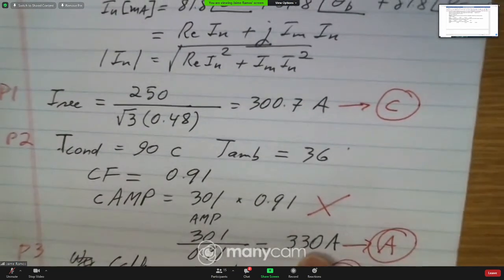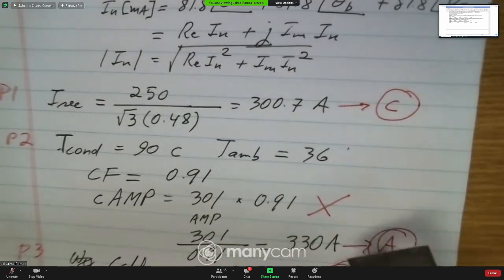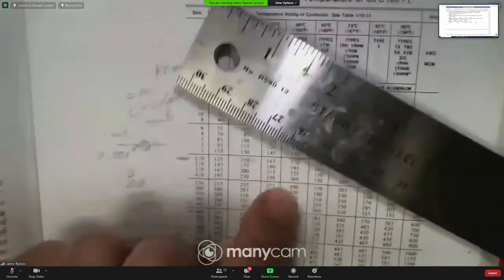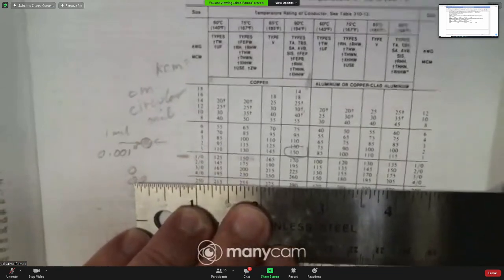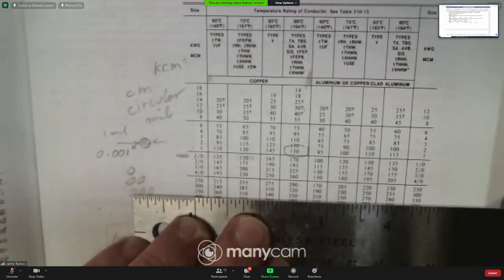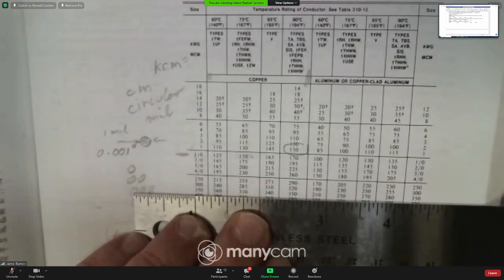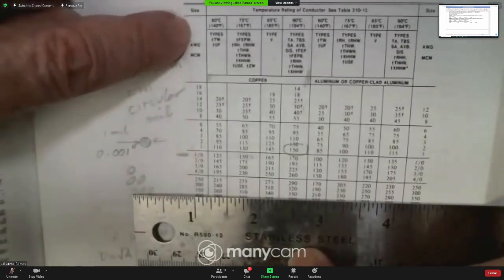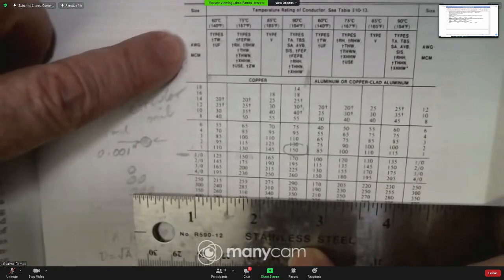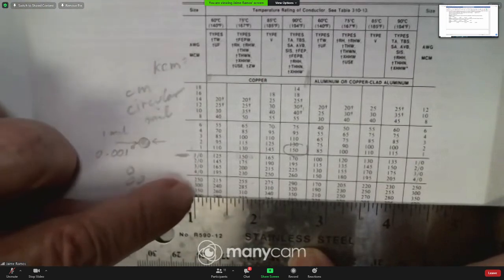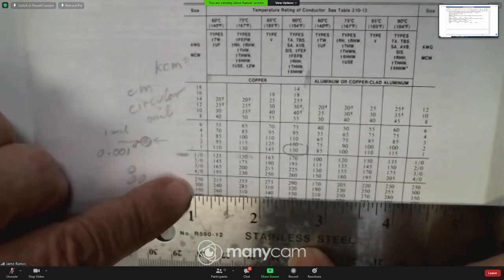So look, when the ampacity was corrected by the effect of ambient temperature, it went up from 301 amps to 330 amps, okay? So now we must look at this number in the table. So now the table, we go to column 90 degrees because that's the temperature of the insulation. And then, so this is 290, 320. So it's between 300 and 350 kcm. I'm reading now here on the first column, which is the type of conductor, the size of the conductor. So it's going to be a cable of 350 kcm.